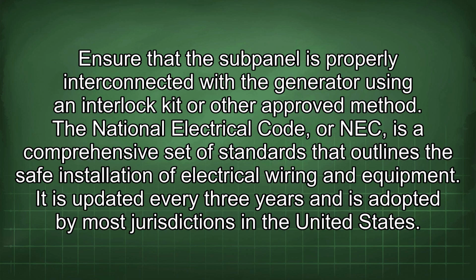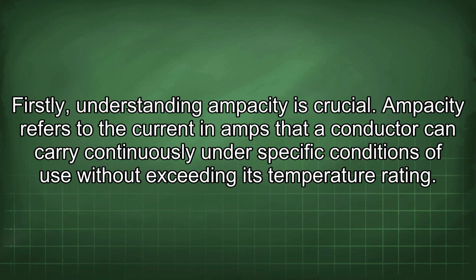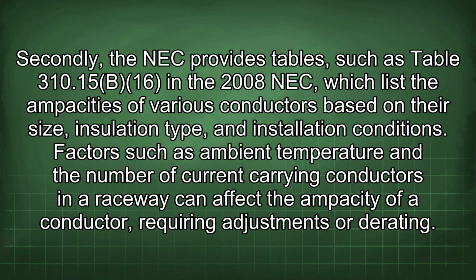The National Electrical Code, or NEC, is a comprehensive set of standards that outlines the safe installation of electrical wiring and equipment. It is updated every 3 years and is adopted by most jurisdictions in the United States. Firstly, understanding ampacity is crucial. Ampacity refers to the current in amps that a conductor can carry continuously under specific conditions of use without exceeding its temperature rating. Secondly, the NEC provides tables, such as Table 310.15(B)(16) in the 2008 NEC, which list the ampacities of various conductors based on their size, insulation type, and installation conditions. Factors such as ambient temperature and the number of current-carrying conductors in a raceway can affect the ampacity of a conductor, requiring adjustments or derating.